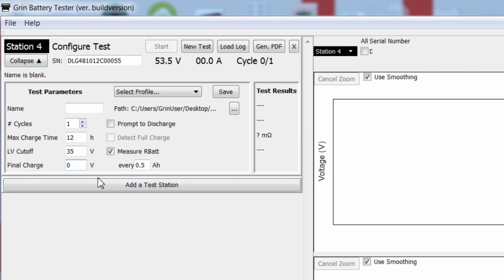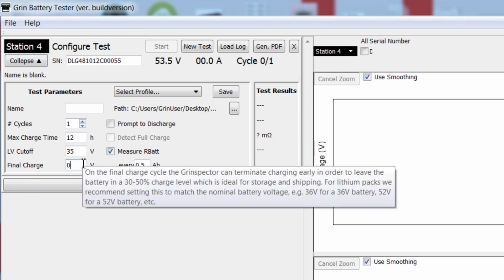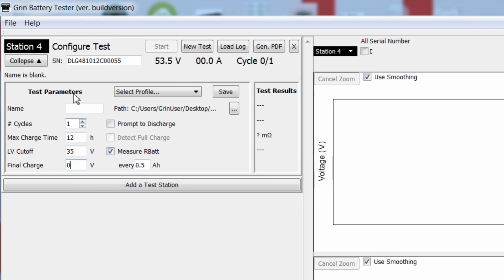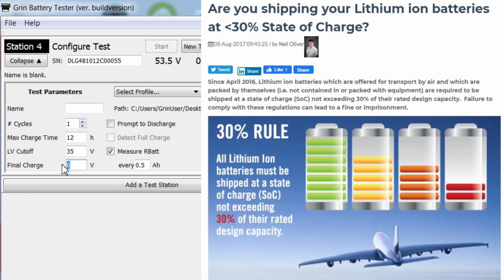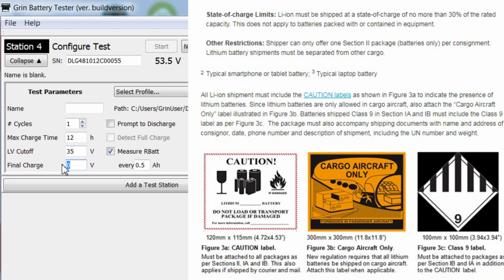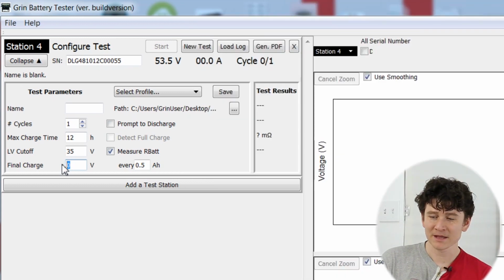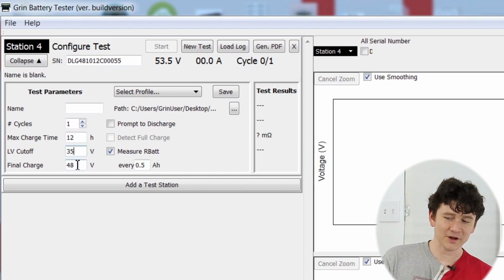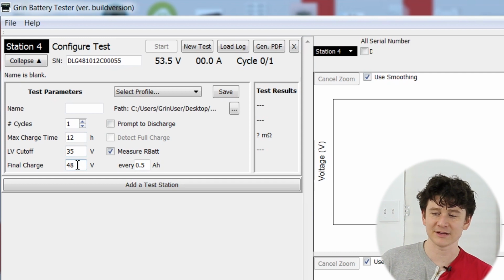This final voltage parameter is interesting. When the final discharge cycle completes, the station connects the charger but doesn't let it charge all the way up if you set a final charge voltage to stop charging early. The reason is that shipping lithium batteries is heavily regulated, requiring the battery be at 30% charge before shipping. This gives a convenient way to prepare a battery, not only to characterize it but to have it in a state ready to ship back to a customer. So on a 48 volt battery, if you set 48 volts as the final charge voltage, stopping charging once it hits that, the battery will be at about 47 volts, right around the 30% charge level.